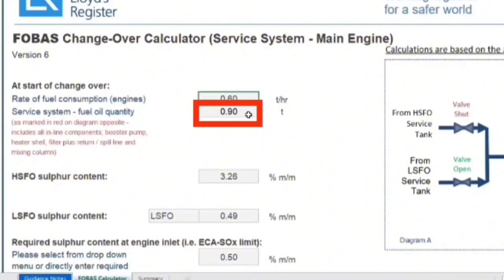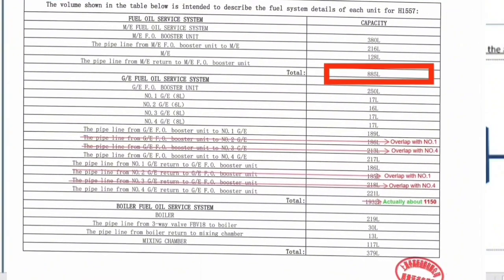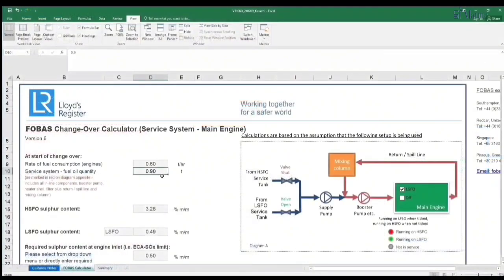The most important data you have to input here is the system fuel quantity. We have to get from the official documents the quantity of fuel in the system. The remaining contents of used oil and new oil also need to be filled in. After that, you will know how many hours are required for the changeover.